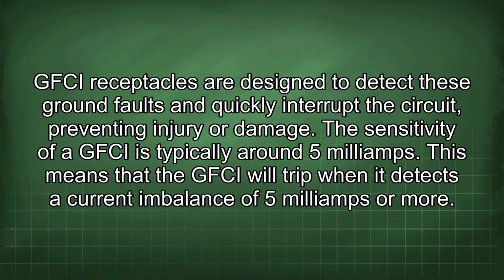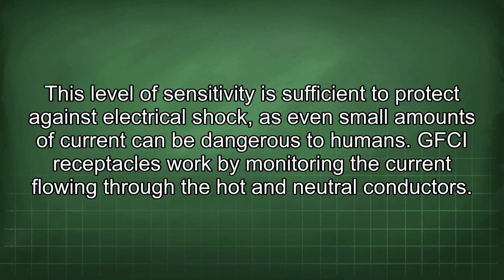The sensitivity of a GFCI is typically around 5 mA. This means that the GFCI will trip when it detects a current imbalance of 5 mA or more. This level of sensitivity is sufficient to protect against electrical shock, as even small amounts of current can be dangerous to humans. GFCI receptacles work by monitoring the current flowing through the hot and neutral conductors.